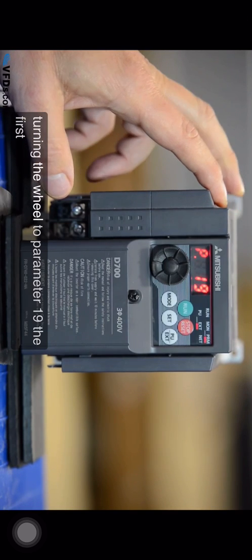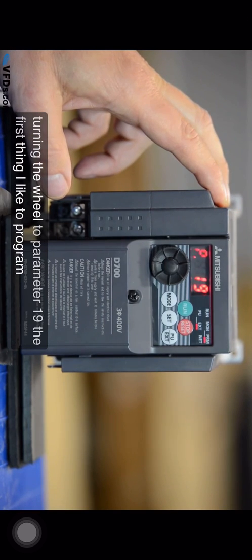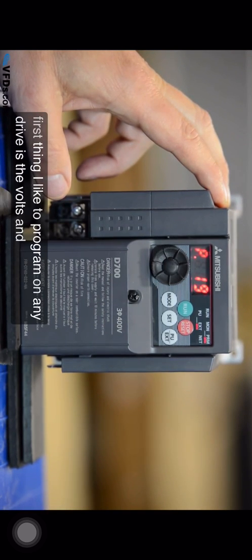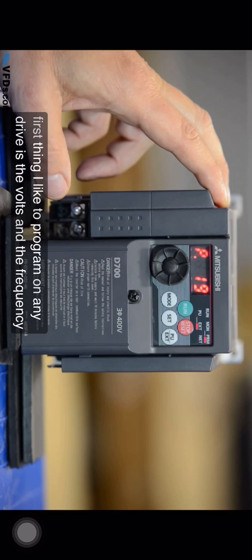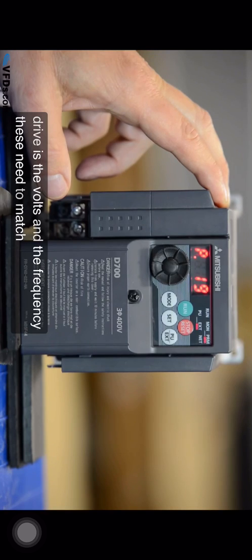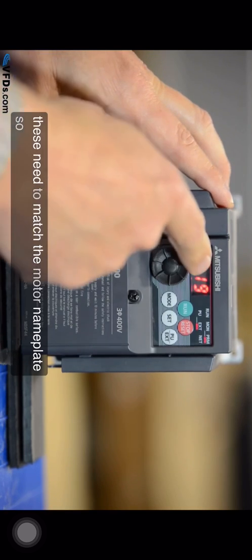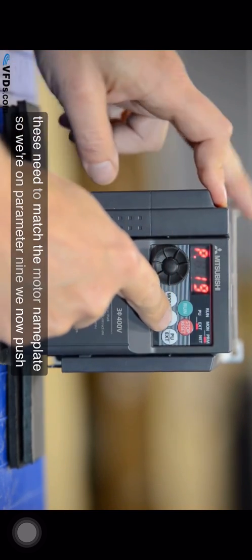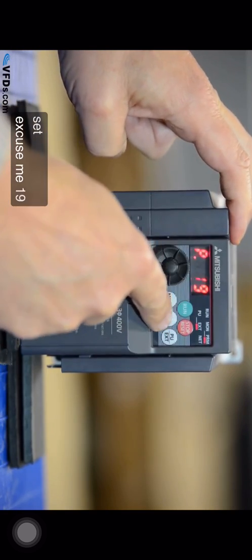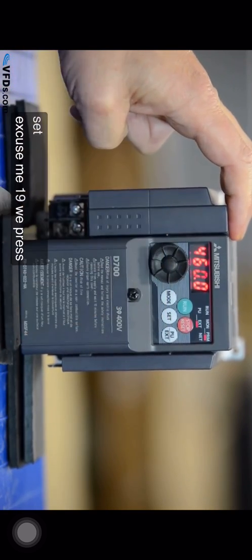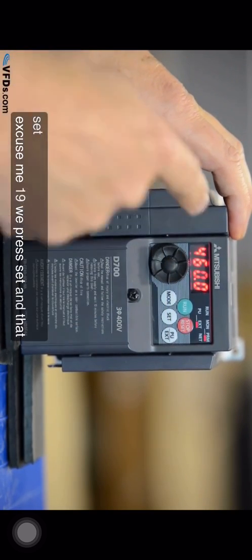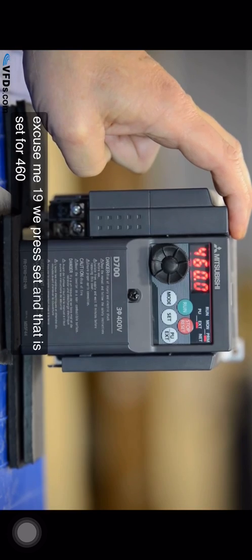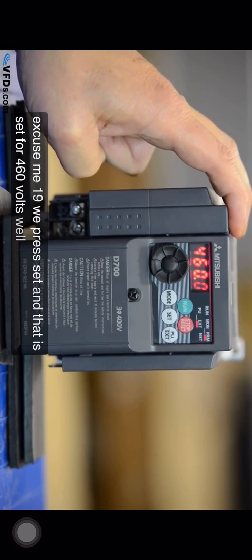The first thing I like to program on any drive is the volts and the frequency. These need to match the motor nameplate. So we're on parameter 19. We press set and that is set for 460 volts.